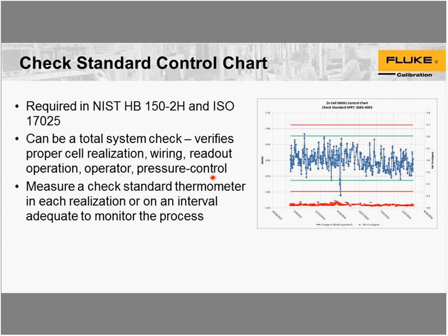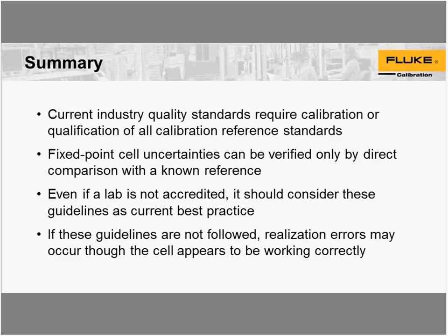In a laboratory, we use a check standard at the base plateau when we're making measurements, and then at the end of the plateau when we're finished calibrating DUTs in the fixed point cell in a reference level fixed point process. In our secondary level fixed point process, where we're using mini cells, we use the check standard at the beginning of each plateau. So with that, we can get to our final slide in our summary.